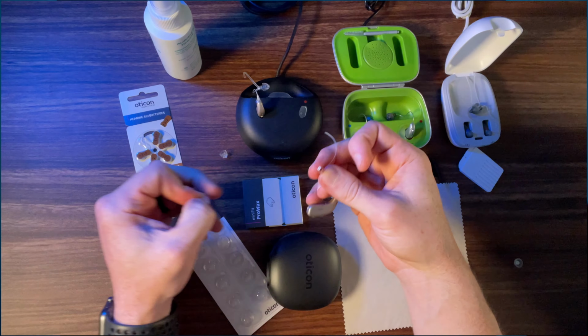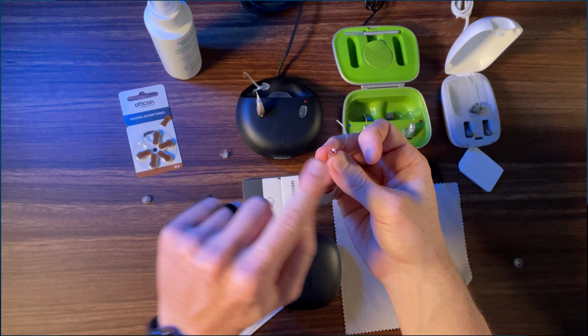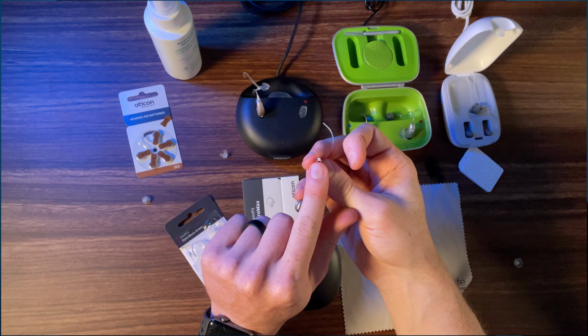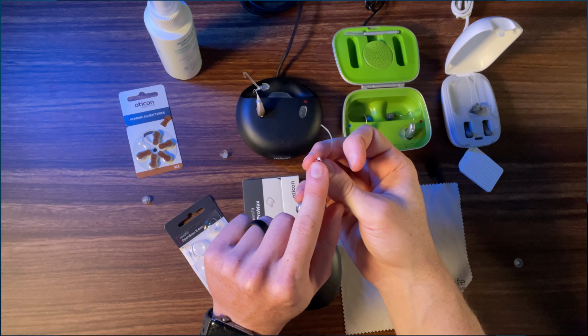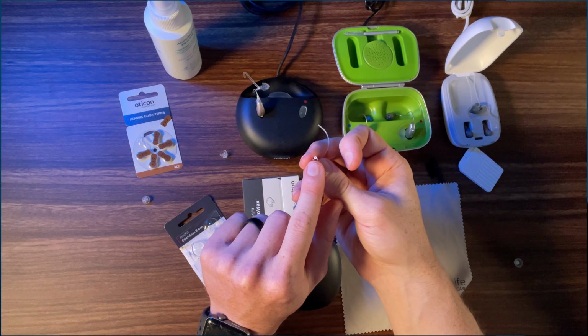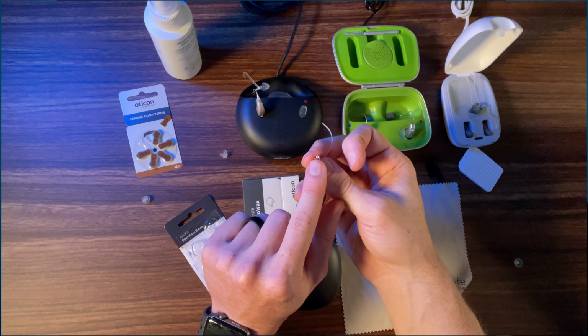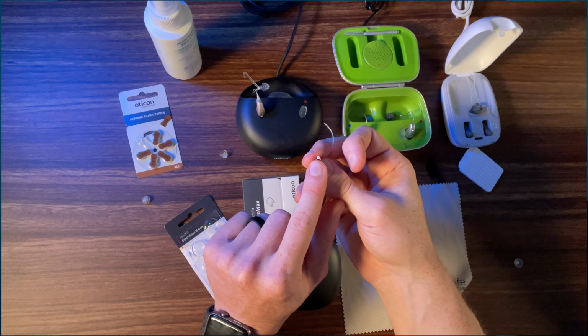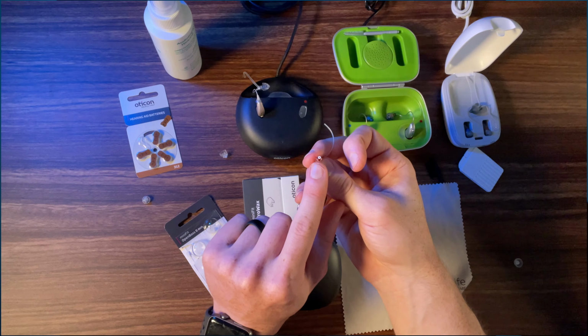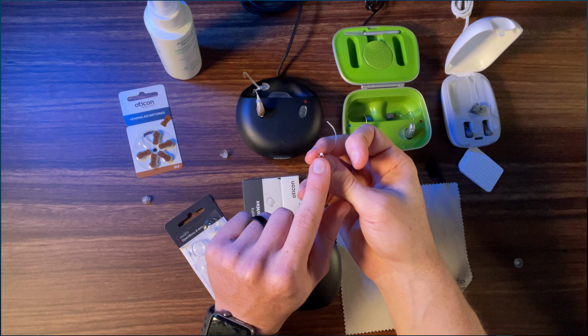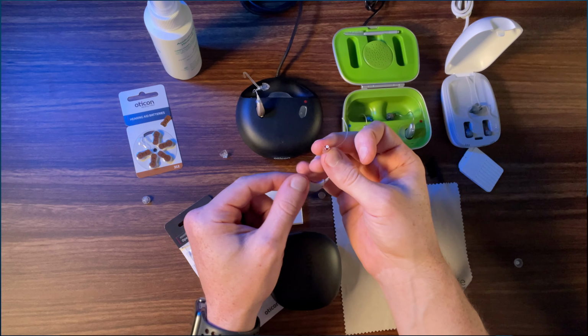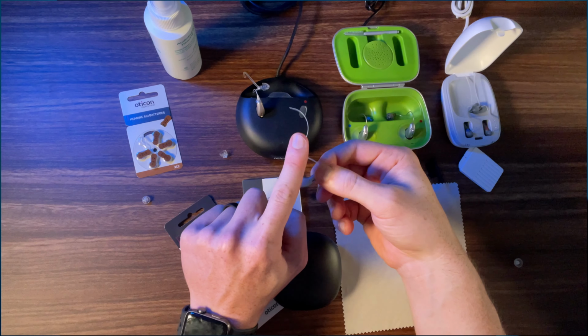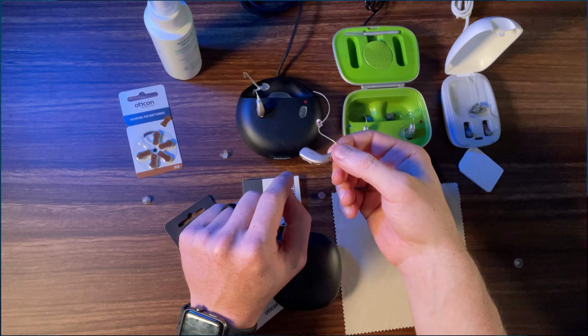So to take that off, underneath is a wax filter. And you're going to see with most receiver in the ear hearing aids, there's going to be a wax filter. The tools that they use to replace the wax filter will vary between manufacturers, but the concept is the same. The purpose of a wax filter or a wax guard is to keep earwax from getting down inside of the hearing aid, which can stop up the speaker and cause sound to stop coming out of the hearing aid.